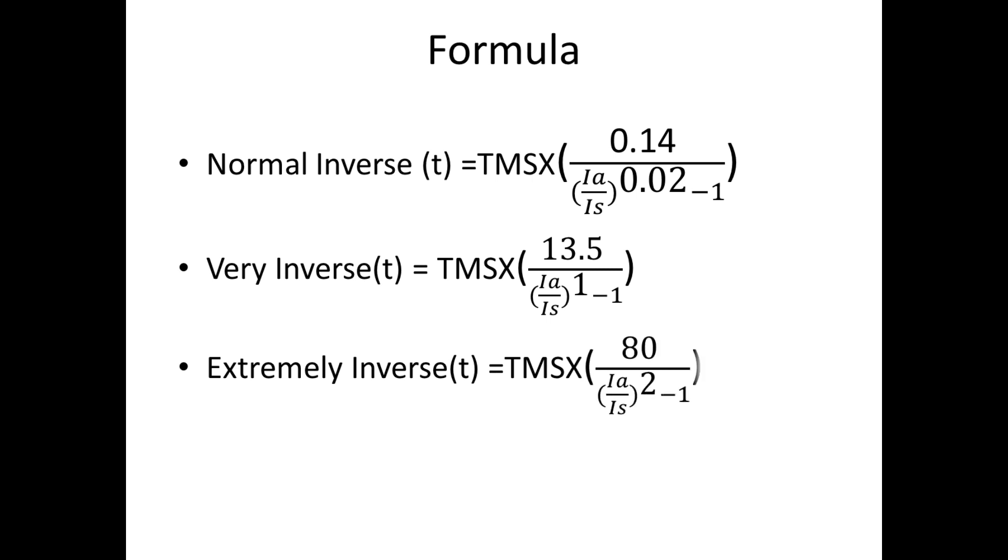And the formula for long time inverse is: TMS times 120 divided by (Ia/Is) to the power 1 minus 1.